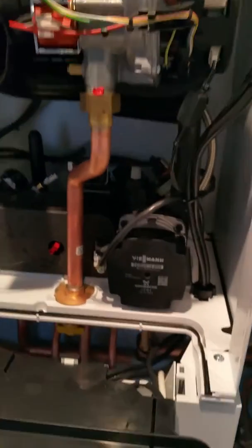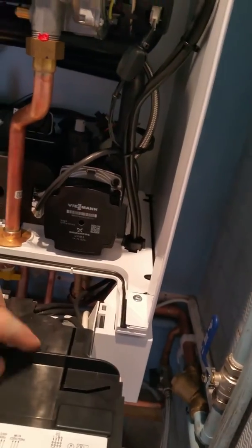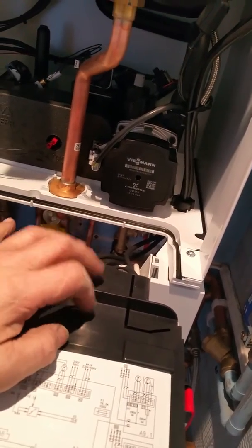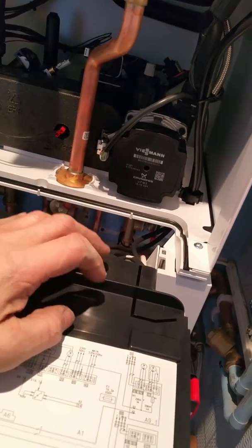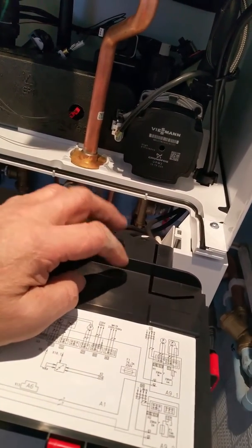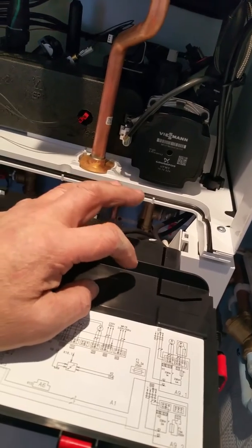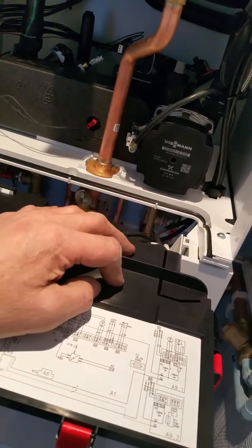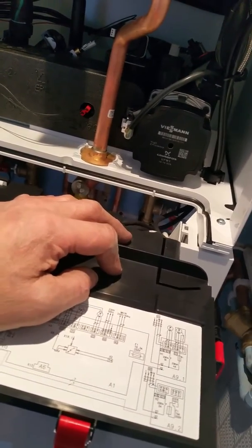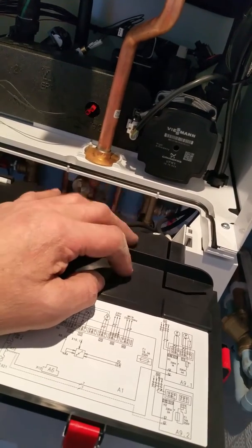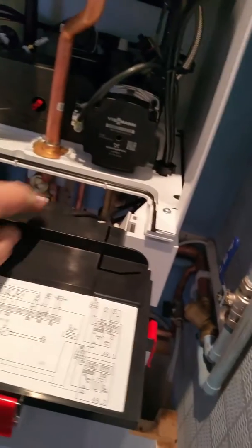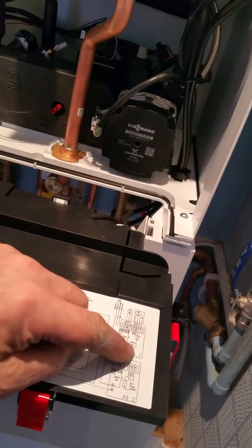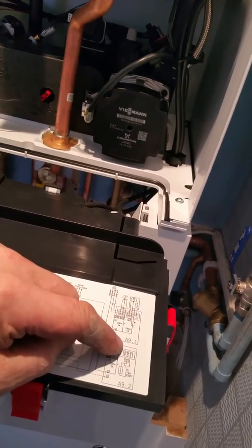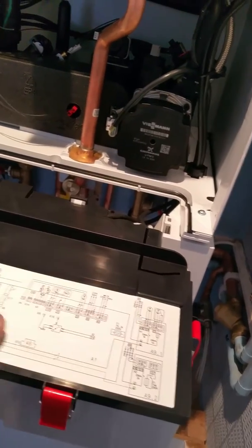Inside though, one down point: they've changed the way the electrical plugs are rigged, so you can't actually test your polarity at the point of entry to the boiler, which is very frustrating. If you turn the boiler on, you must have it wet, which I didn't have when I wanted to do my electrical tests, so that's a pain. I've had to cut the mains lead from the boiler, using the relay position here, cut and shut it, and place it in there.